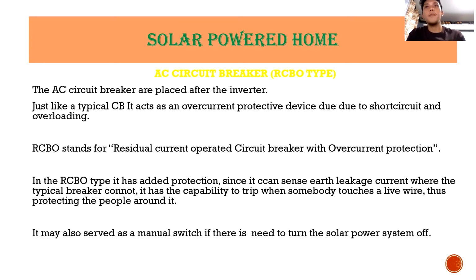Next is the AC circuit breaker or RCBO type. The AC circuit breaker is placed after the inverter. Just like a typical CB, it acts as an overcurrent protective device against short circuit and overloading. RCBO stands for residual current operated circuit breaker with overcurrent protection. The RCBO type has added protection since it can sense earth leakage current where a typical breaker cannot. It has the capability to trip when somebody touches a live wire, thus protecting the people around it. It may also serve as a manual switch if there is a need to turn the solar power system off.